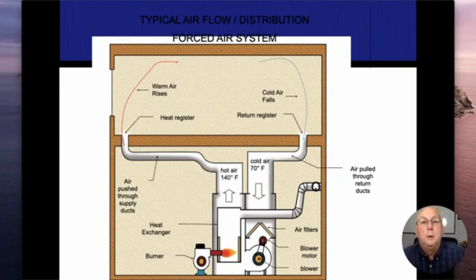All right. So here we're going to switch over to forced air furnaces. And this is actually an oil furnace. So anytime I get that blow dryer looking object in any diagram, that's pretty much an oil burner that we're looking at. And if I come up here to the right side, right above the dot there, you can see that's our barometric damper that we talked about earlier. All right. Now, airflow into forced air furnaces is important. All right. And it should always be the same way.